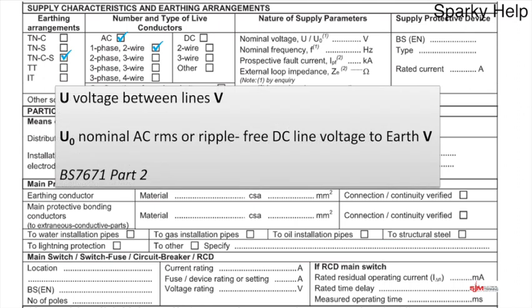Let's look across to the next bit then, nature of supply parameters. The first one it asks for is nominal voltage, and we have these letters in here, U/U0, which has number 1 in brackets beside it, and it says by enquiry. I would suggest if you're doing this by enquiry, probably don't be looking at doing the testing yourself, because you're probably not that competent unless it happens to be abnormal. But let's go look at what U means.